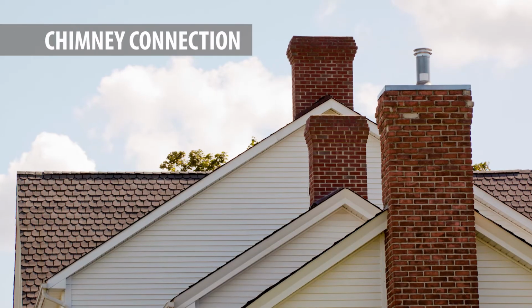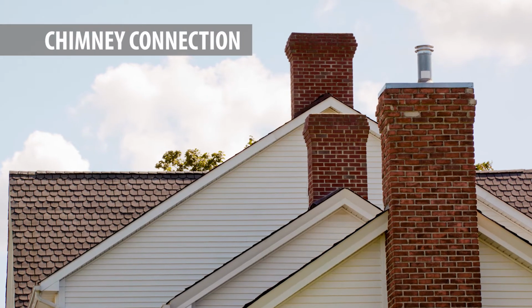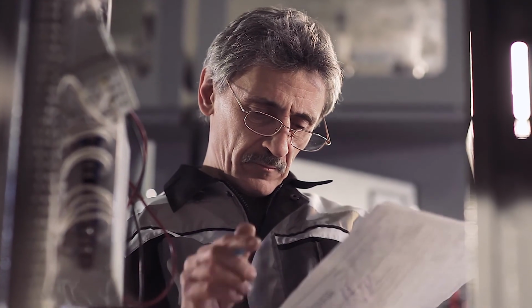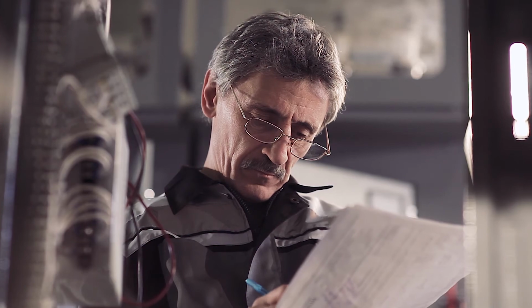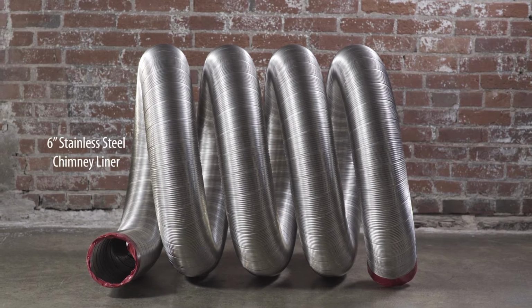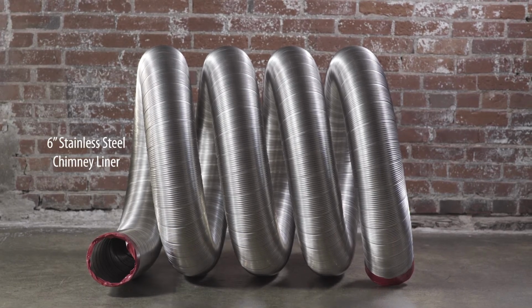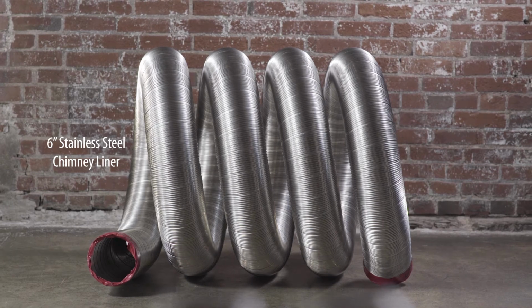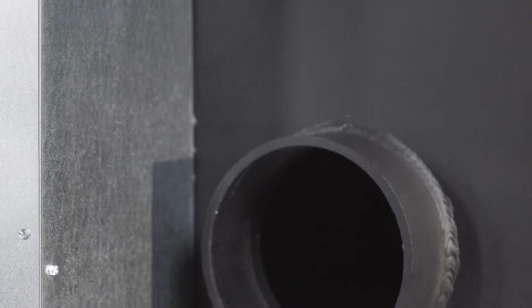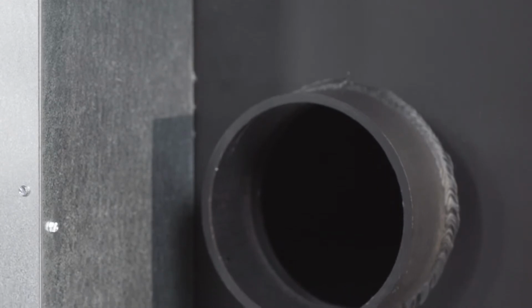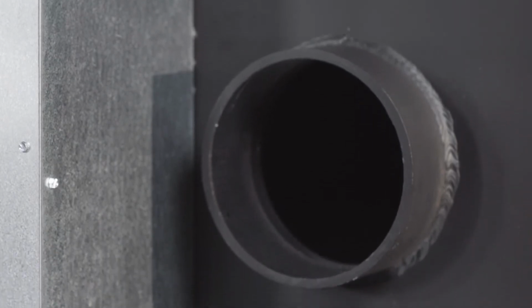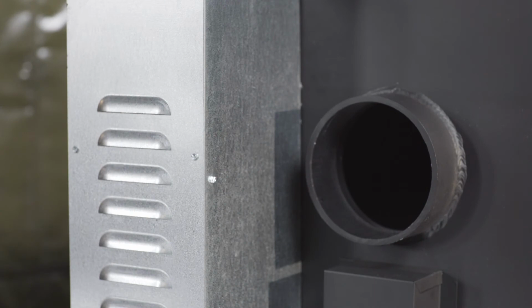Next, you will need to connect your furnace to a properly functioning chimney. If connecting to an existing chimney, we strongly recommend the chimney be professionally inspected to ensure it is in proper working condition. It is critical that the chimney is properly sized to maximize the performance of your furnace. Lining an existing chimney with a 6-inch stainless steel liner is strongly encouraged and may be required by local authorities. All Fire Chief EPA-certified wood-burning furnaces are equipped with a 6-inch flue exit. Never connect to a smaller diameter flue or a chimney that services another appliance.